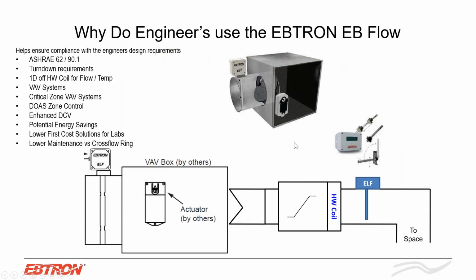Why do engineers use the EBTRON EB Flow? Again, so this is what I was showing on the previous slide right here in the center. Well, turn down requirements can meet that. If you're trying to save energy based on 90.1, any type of critical zone VAV systems, this is a really high performance VAV box, and it's going to help with potential energy savings, right? Also, this is a lower first cost for lab type of applications. Basically, we are the VE for labs because this is such a high performance flow meter right here.